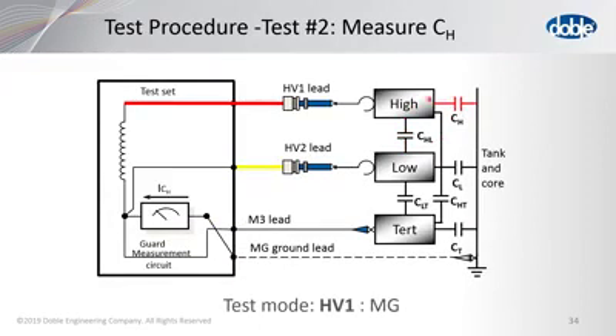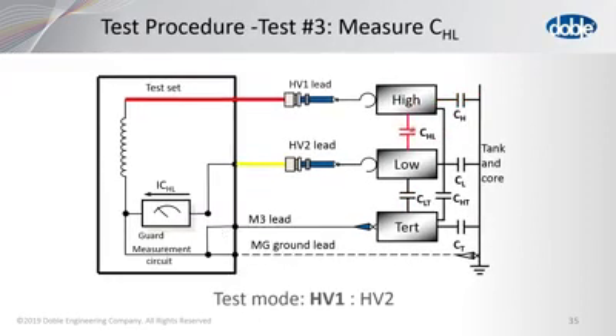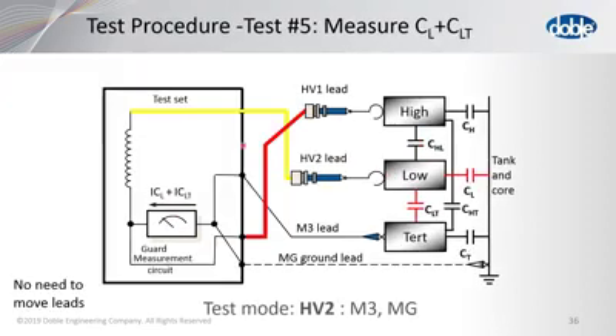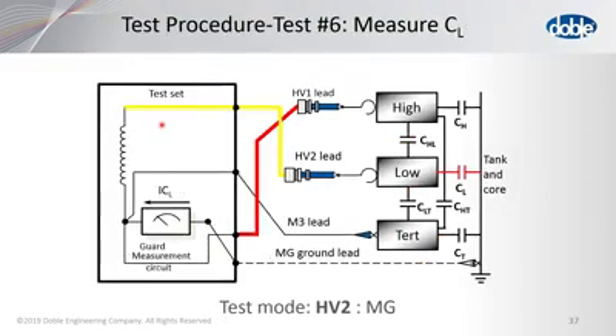Then test number 2, we only measure CH. And then test number 3, we measure only CHL. Notice that high voltage lead 2 is actually a measurement lead now. Then we do not have to change the lead connections. So in other words, you don't have to go back up on the transformer to do tests 5, 6, and 7. And that's done this way. So you energize the HV2 lead, and these 2 insulation systems are energized, and you will measure those. And then the test set continues on with its multiple tests.